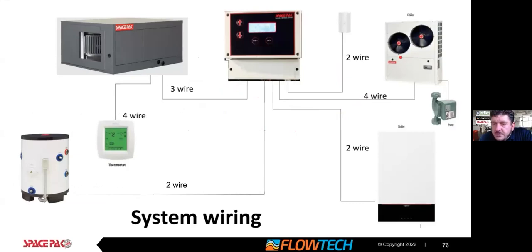At the very basics, it's taking calls from the field. So you have an air handler, like right here, we have a SpacePak air handler tied to a thermostat, or perhaps a zone control from a radiant floor heating system. It's landing up to 5 zones of heating and cooling calls. Those are 24-volt heating and cooling calls from the field. And I don't know why this image changed. It had a new unit in there. This is our older unit, but nevertheless, the SSIC will turn the unit on when appropriate. It'll turn it into the correct mode, whether it's heating or cooling. So it provides that critical switchover from heating to cooling mode based on calls from the field. That's the basic step there too.